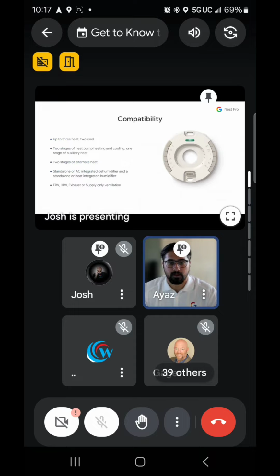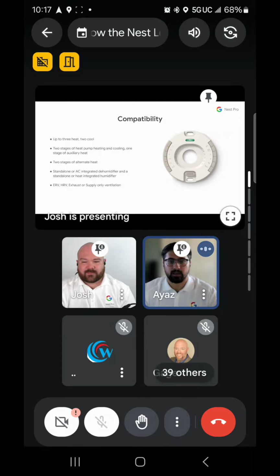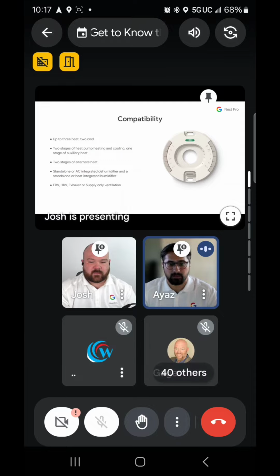The Nest Learning Thermostat 4th Gen is compatible with more systems than before, including up to 3 heat, 2 cool on a conventional system, and 2 stages of heat pump heating and cooling, 1 stage of auxiliary heat, or 2 stages of alternate heat. It's also compatible with standalone or AC integrated dehumidifiers and a standalone or heat integrated humidifier. And for the first time ever, this Nest Learning Thermostat 4th Gen is compatible with ERV, HRV, exhaust, and supply-only ventilation systems, thanks to those new AQ Plus and AQ Minus terminals.